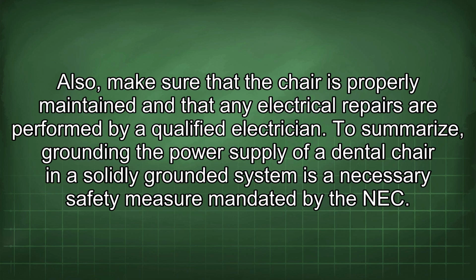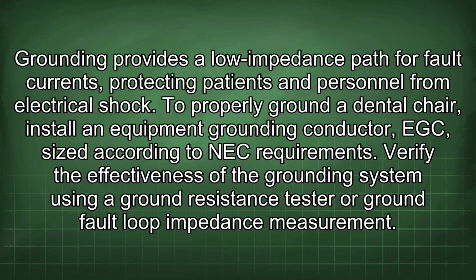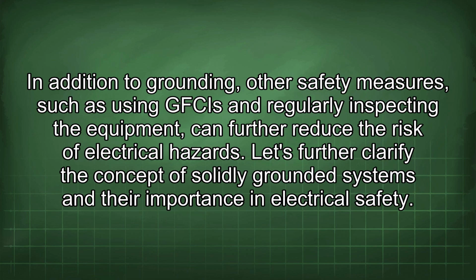To summarize, grounding the power supply of a dental chair in a solidly grounded system is a necessary safety measure mandated by the NEC. Grounding provides a low impedance path for fault currents, protecting patients and personnel from electrical shock. To properly ground a dental chair, install an equipment grounding conductor, EGC, sized according to NEC requirements. Verify the effectiveness of the grounding system using a ground resistance tester or ground fault loop impedance measurement. In addition to grounding, other safety measures such as using GFCIs and regularly inspecting the equipment can further reduce the risk of electrical hazards. Let's further clarify the concept of solidly grounded systems and their importance in electrical safety.